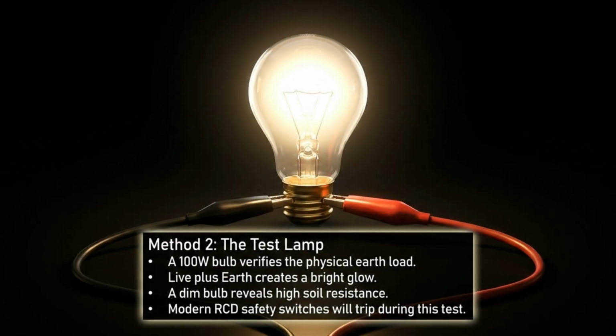Method 2 uses a test lamp. A 100-watt bulb verifies the physical earth load. Connecting the live and earth should create a bright glow. Be aware that modern RCD safety switches may trip during this test.